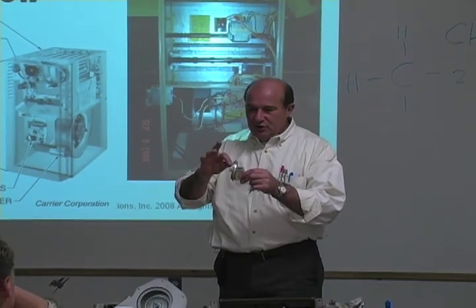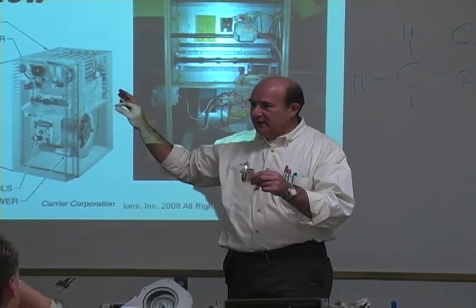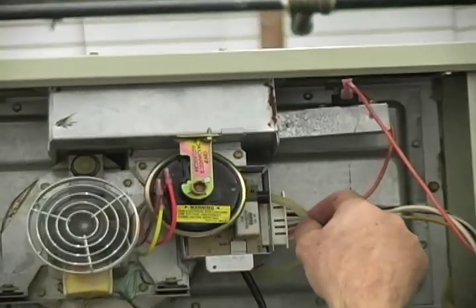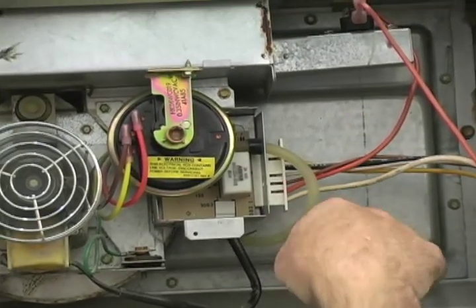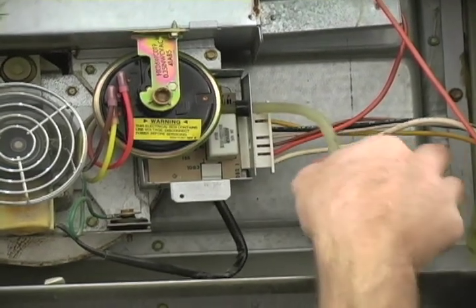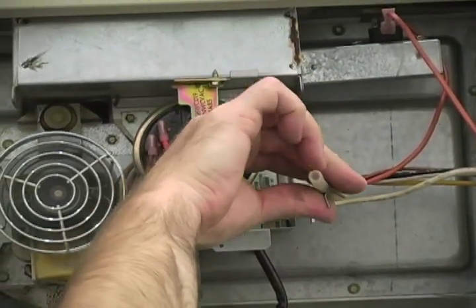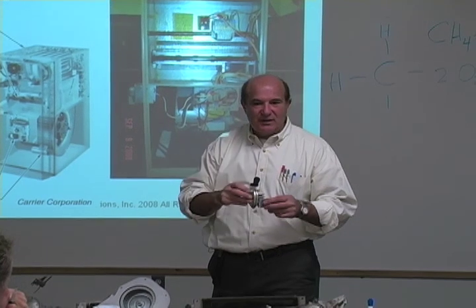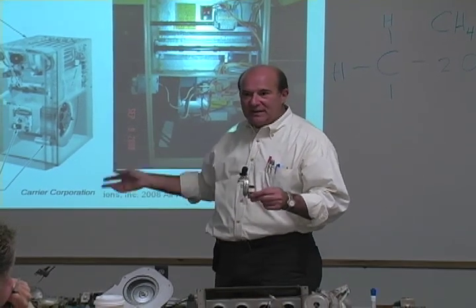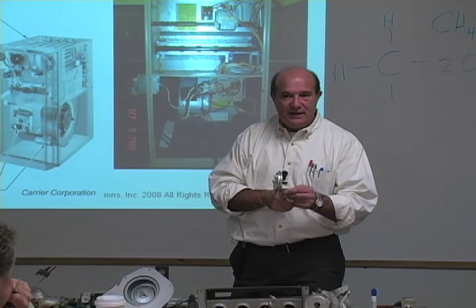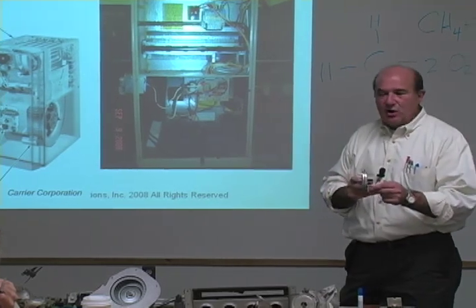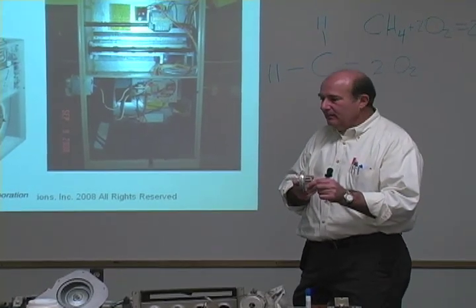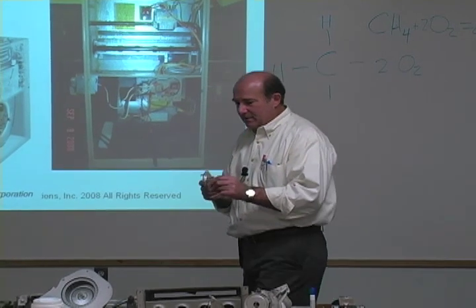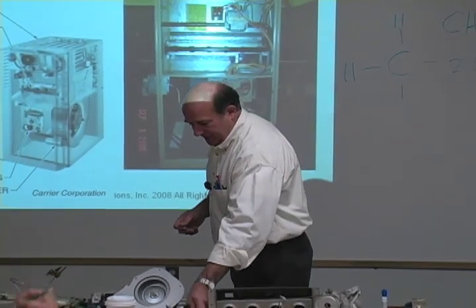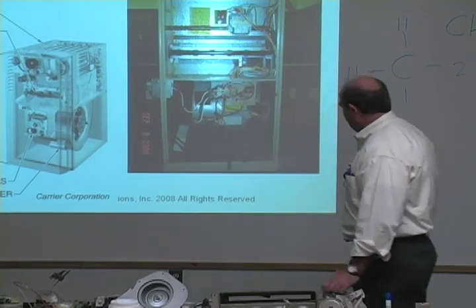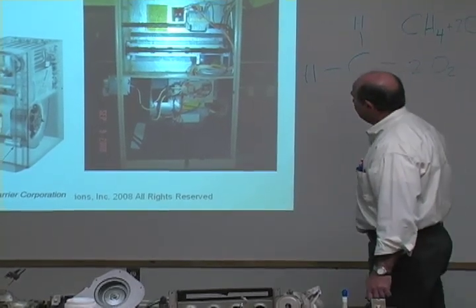What we do is we connect a tube from this pressure switch to the inside of the heat exchanger, and as that fan comes up to speed and creates a negative pressure in there, that negative pressure draws against this opening here, and it closes a little switch. And what it does, it tells the furnace, the gas valve, that yep, our combustion blower is running, the fan is on, and it's okay to fire up the gas valve. So that's the second major component in a fan assist or 85% furnace.